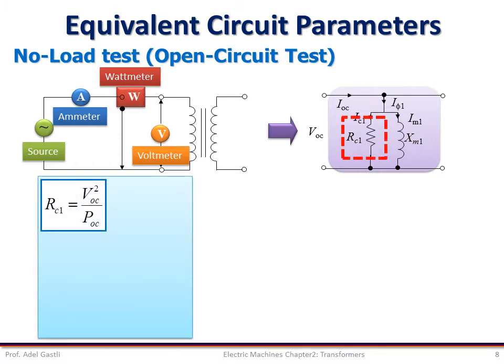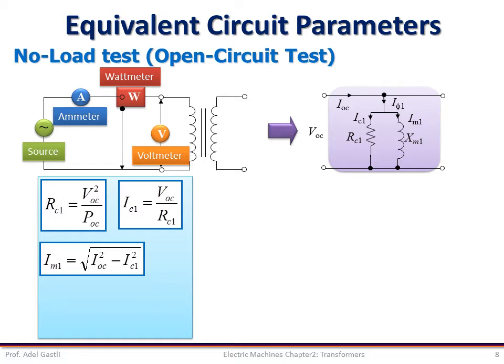Using this equivalent circuit, we can deduce the core loss resistance RC1 as the ratio of the square of the open circuit voltage VOC squared over the measured open circuit power POC. The current IC1 in the core loss resistance RC1 is equal to the ratio of the voltage and the resistance RC1. Then we can calculate the magnetizing current RMS value IM1 as the square root of the difference between the square of the total input current I_OC and the square of the core loss current IC1. Finally, the magnetizing reactance XM1 can be calculated as the ratio of the open circuit voltage VOC over the magnetizing current IM1.